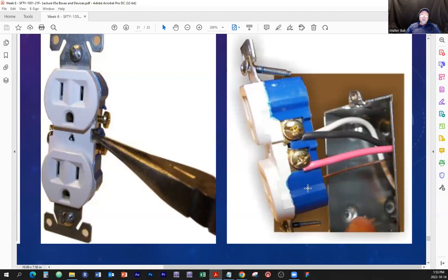The jacketing is pinched. So it's touching the screw terminal. Not only touching, it's actually pinched by the screw terminal. So the screw terminal is making contact with the jacketing and not as much contact as we want to, possibly, with the rest of the connector. Squished. There we go. That's another good thing. Okay. All right.